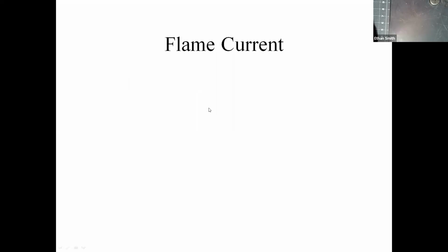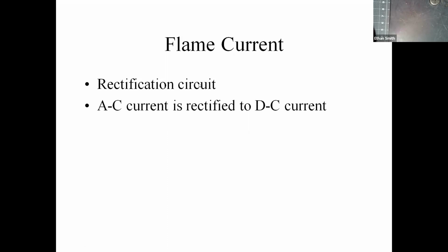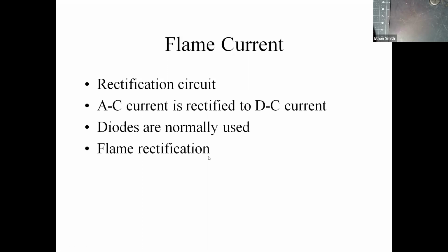We talked about diodes. So the reason we talk about diodes is what we're doing when we check flame current. So flame current is actually an electrical property. We're using a rectification circuit, just like we used with diodes. We're changing AC voltage to DC voltage, but we're using the actual flame of a burner. Flames have this interesting little property that they will actually rectify AC to DC current.